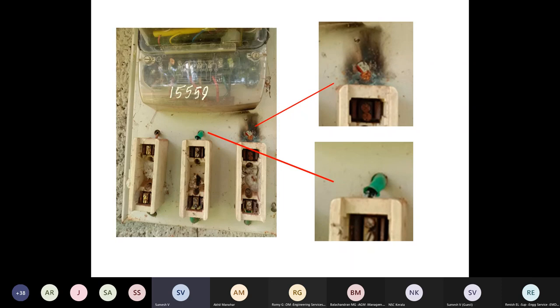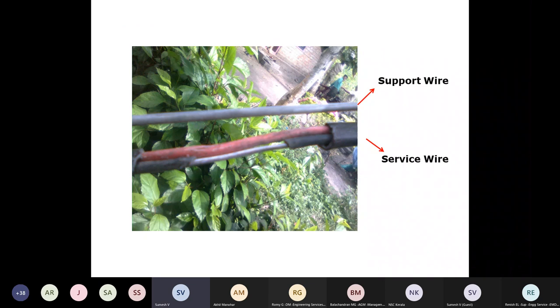metal panel. Then another reason for electrical accidents in domestic premises is the service wire. A service wire is not supposed to have any joints, but unfortunately, almost all service wires in Kerala have some joints in them. Also, the service wire is accompanied by a metallic support wire. If there is any joint in the service wire, that joint may come in contact with the support wire. Thus, supply may come to our premises, which may cause an accident. So it is better not to use a metallic support wire. Or if a metallic support wire is used, ensure that there is no exposed joint in the service wire.